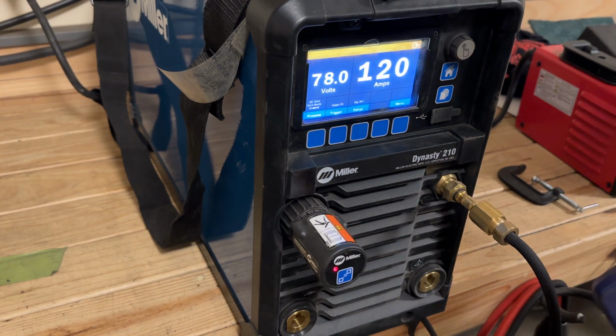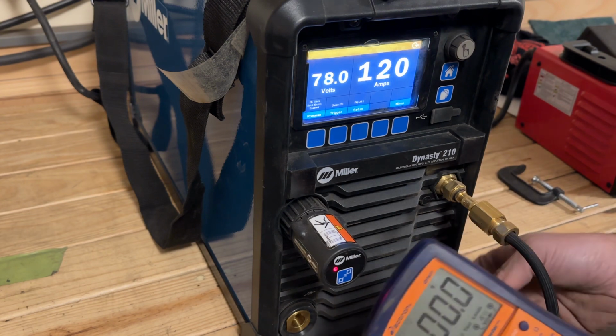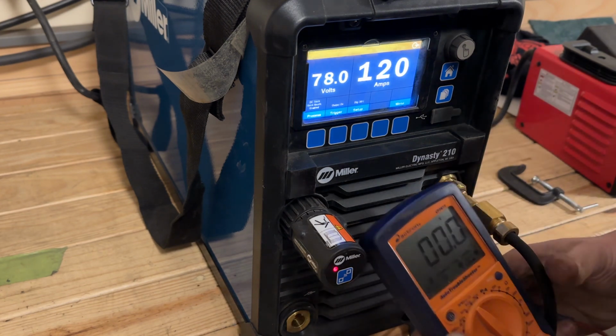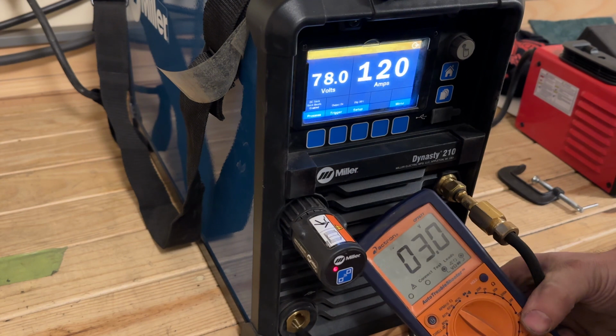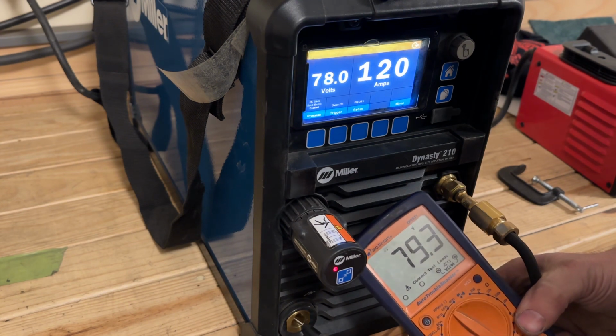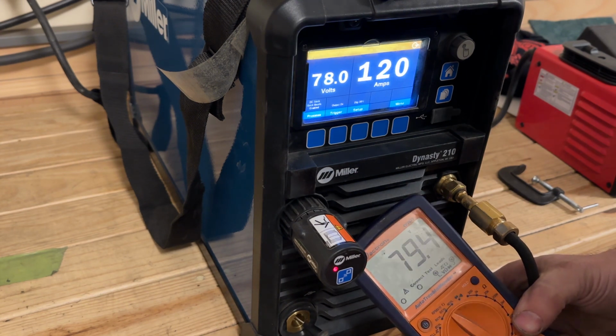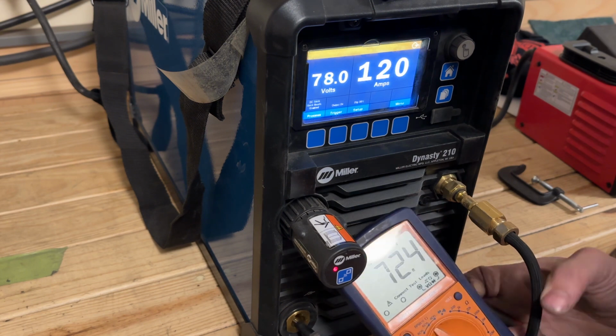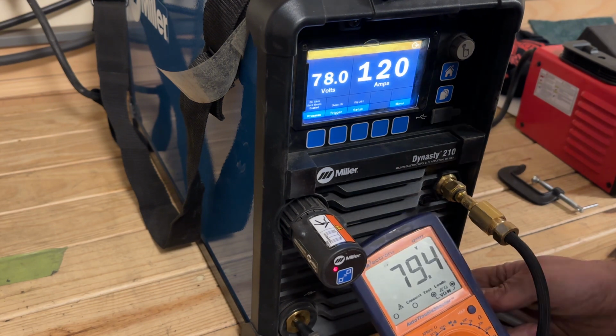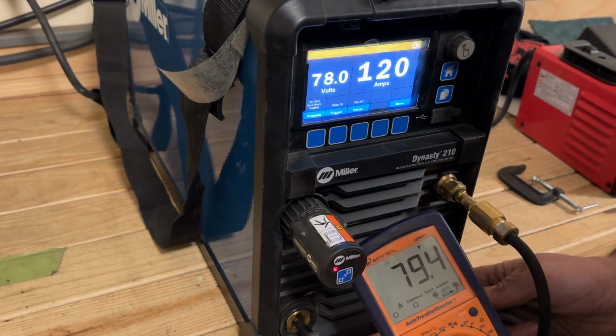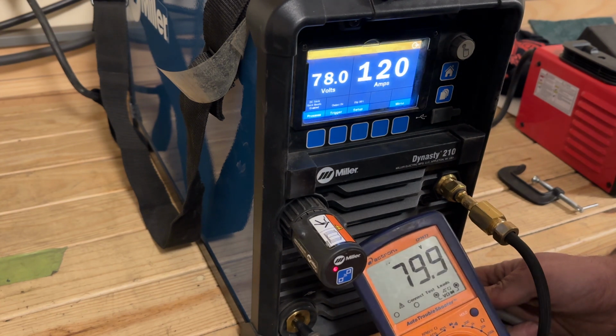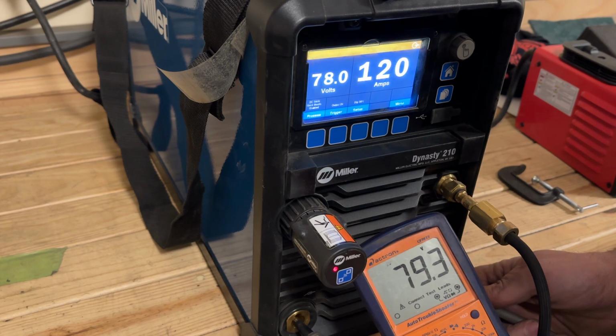So what we're gonna do is go from the positive—I'll set this where you can see it—to the negative. This is reading 79.3, 79.4, so the meter on the machine is close, not quite. This is reading a little bit higher. Which one's more accurate? Who knows? But we're at about 78, 79 volts.